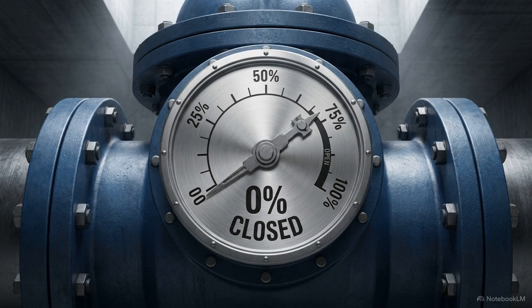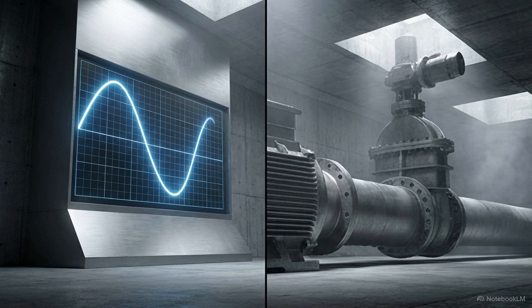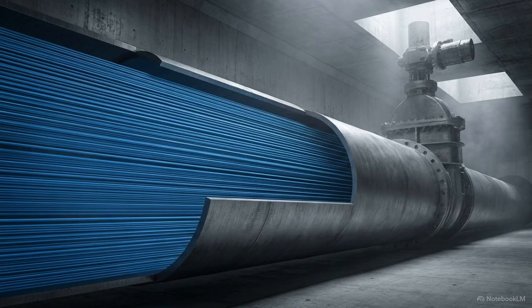The 600mm motorized discharge valve begins to open, taking a rigidly timed 5 minutes to transition from fully closed to fully open. Combining the electrical current dampening of the FCMA with the deliberate 5-minute mechanical valve rotation ensures the thousands of tons of fluid in the pipeline gradually accelerate, actively suppressing any chance of sudden hydraulic shock.